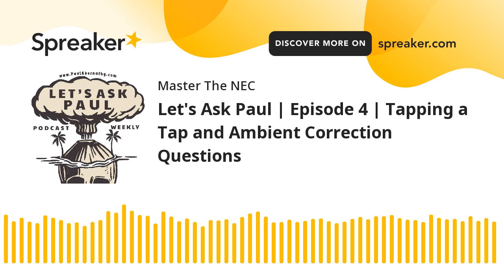So we have been given the permission to tap a feeder. However, there are rules we have to follow. Why? Because feeders, like any other conductor, have to be protected at their ampacity. So you've got a panel with a breaker in there, and that is a feeder breaker feeding maybe a panel downstream, and that's a feeder. Now we're going to be tapping that feeder, and we have to follow these rules. There are a certain number of rules that you have to follow.